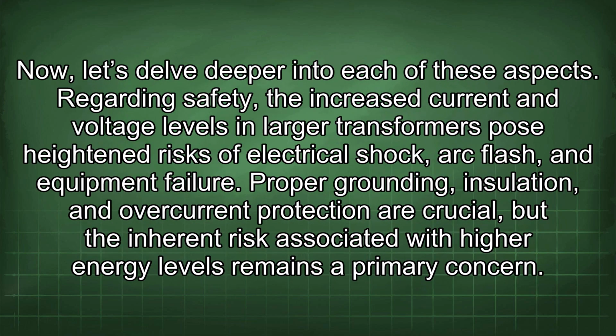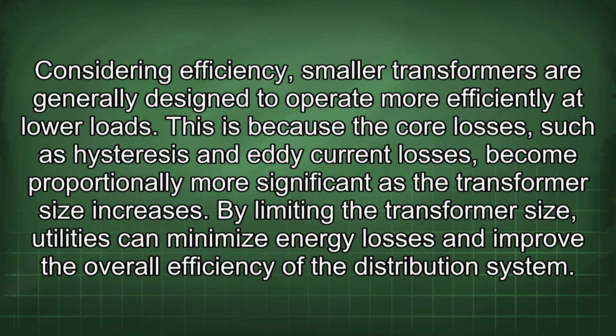Now let's delve deeper into each of these aspects. Regarding safety, the increased current and voltage levels in larger transformers pose heightened risks of electrical shock, arc flash, and equipment failure. Proper grounding, insulation, and overcurrent protection are crucial, but the inherent risk associated with higher energy levels remains a primary concern. Considering efficiency, smaller transformers are generally designed to operate more efficiently at lower loads.